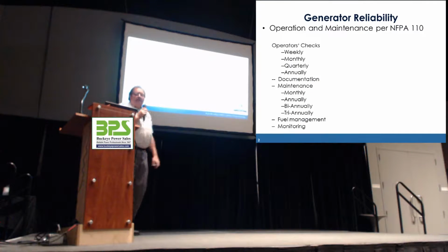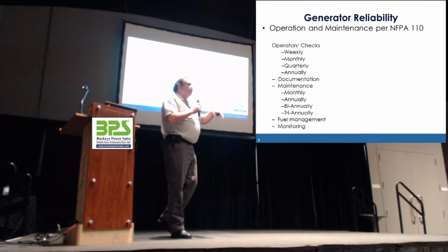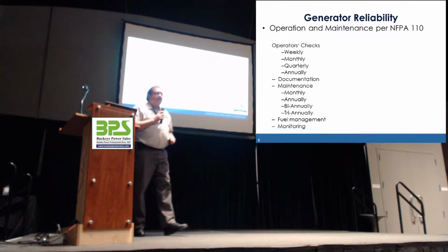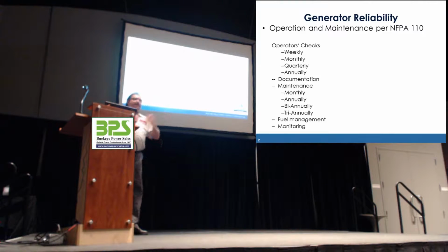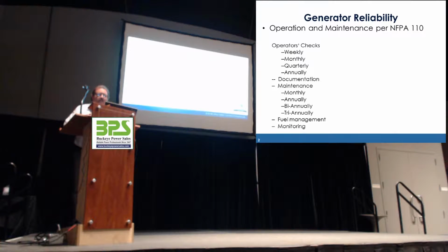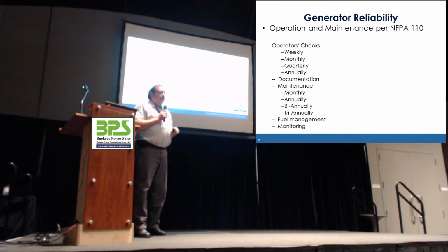So we're going to talk about what the responsibility is of the operators at your facility and what the maintenance requirements are that need to be done to the equipment, the testing that is to be done with the equipment. So we have weekly tests, monthly, quarterly, annual checks. We're going to talk about the documentation that you need to keep, and we're going to talk about the maintenance that needs to be done, everything monthly, annually, every 2 years, every 3 years, in addition to fuel management, monitoring, etc.